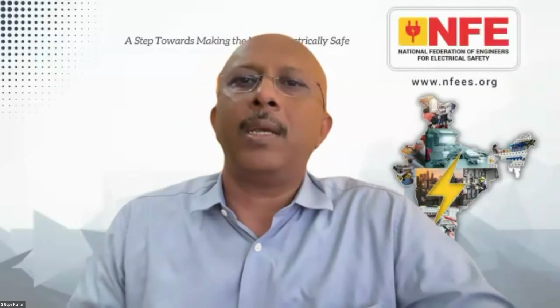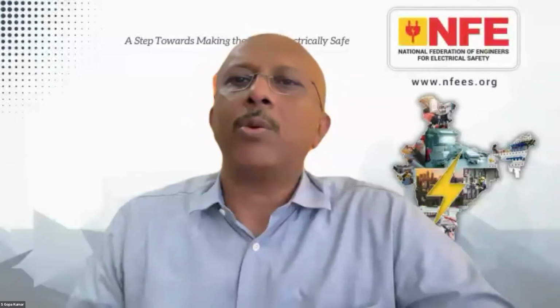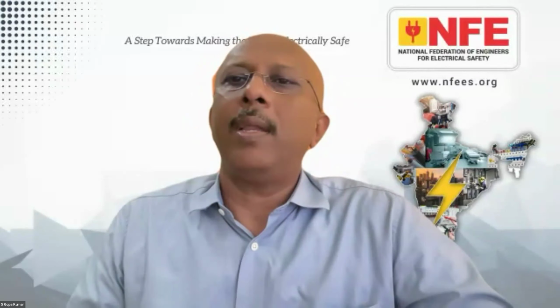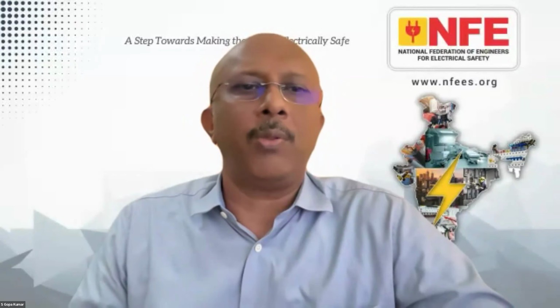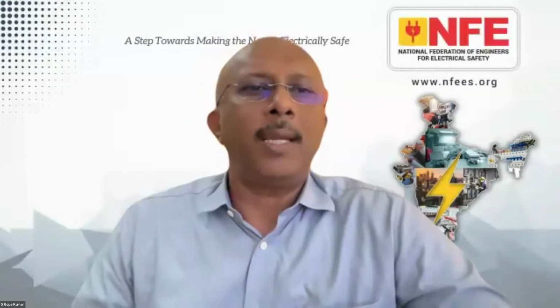Mr. Ravi is asking, in earth fault also the live conductor has an earthed path, so what is the difference between leakage and earth fault? So Krish, you can throw some light on leakage fault. See, earth fault is current that flows in the event of a fault. I'll just share my screen and you can see the definitions on Electropedia.